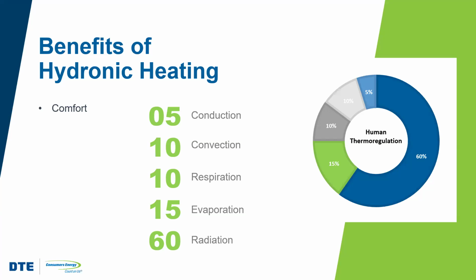Well, you notice in the chart here that the primary way that we give off heat is through radiation, right? And we're giving off heat to the surrounding surfaces: the walls, the floor, the ceiling, the windows in the room that we're in, the bookcase across the room, the computer that's sitting in front of us. One of the interesting things about the hydronic system is that it also operates largely through radiation. Now, it can use forced air as well, and we'll talk a little bit about that later. But the most common hydronic system uses radiation as its primary means of heat transfer. In contrast to a forced air system that heats up the air and then moves that air around the house, hydronic systems use radiators and sometimes convectors as well, that radiate heat to those surrounding surfaces.